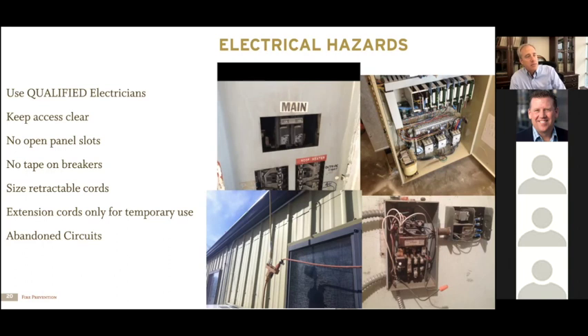away from these panels. Also, in an emergency, you may need to be able to access that electrical panel. And so you want to make sure that you aren't blocking that access to those panels. We want to make sure that we don't see tape over breaker switches. I'll show you an example of that in a minute, and we'll talk about why that's dangerous. And also make sure that your extension cords are proper, the right size for the job, and in condition to be able to handle the load that you're putting on them.